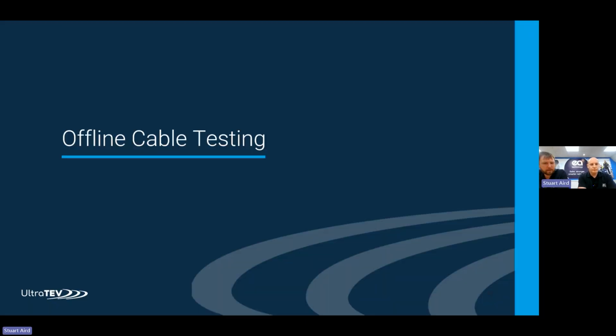Offline testing still has a place. We've talked about how much the handheld devices have moved on. When we talk about offline testing now, this isn't our kit, we're using a third-party kit to support our customers. There are some cables and switches where you can't get access to the terminations, and other cases where you've found PD and want to confirm the location before you dig, or overlay. This is where offline cable testing comes in.